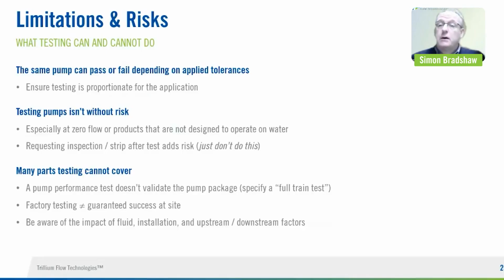So some other things to consider. What testing can and cannot do. As we showed earlier, the same pump, depending on the tolerances that you apply, can pass or fail, because the allowable tolerances for the head and flow, the power, and the efficiency are different for each of these. When you test pumps, it isn't without some risk. I'll say I routinely get customers who want to run pumps that are absorbing 2, 3, 4, or even higher megawatts of power, and they want to see these run at zero flow. That's generally not a good thing.